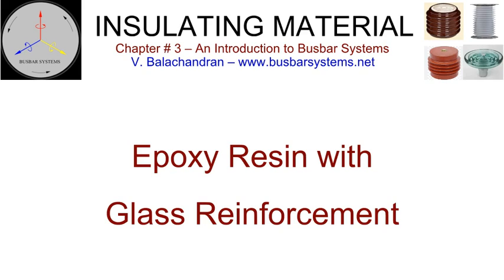Hollow cylindrical or conical components can be made by filament winding. Filament wound cylinders are used as housings for the composite insulators, transformers, bushings, outdoor instrument transformers, and lightning arresters. High-strength, long, profiled insulating components are manufactured by a process called pultrusion.